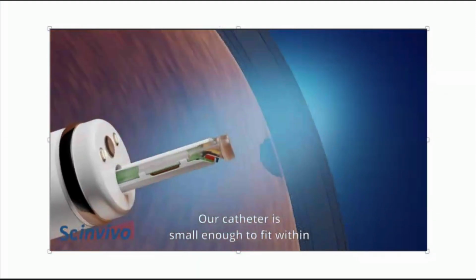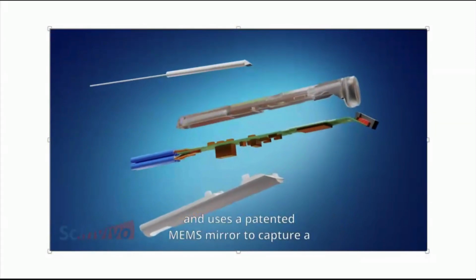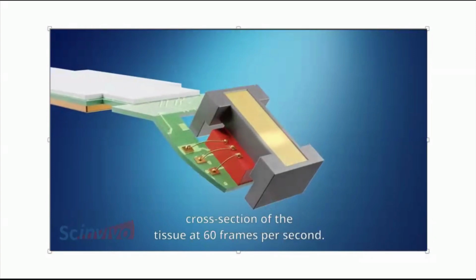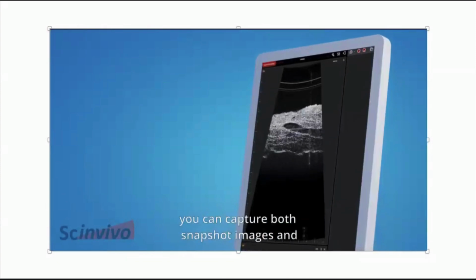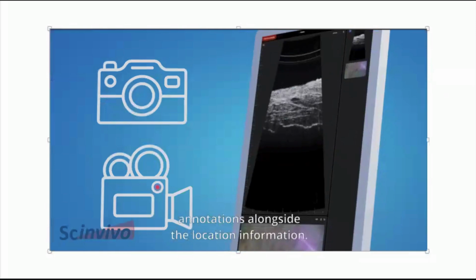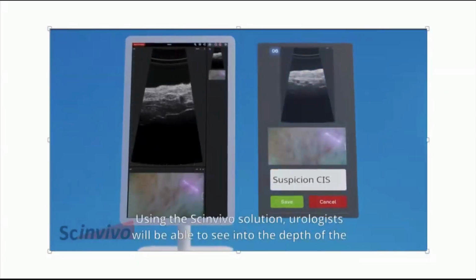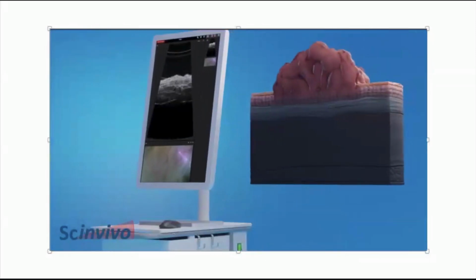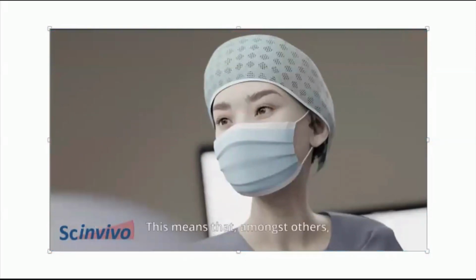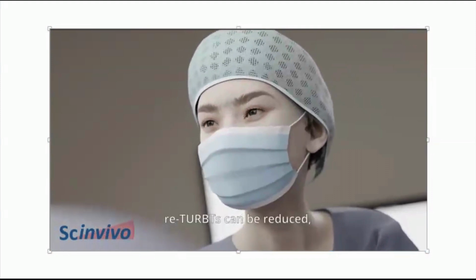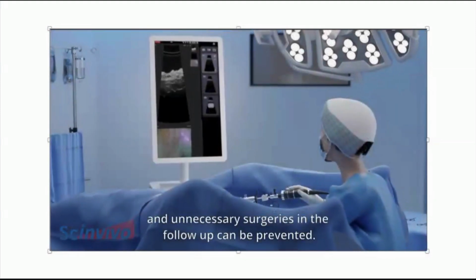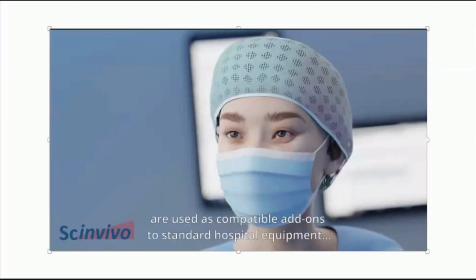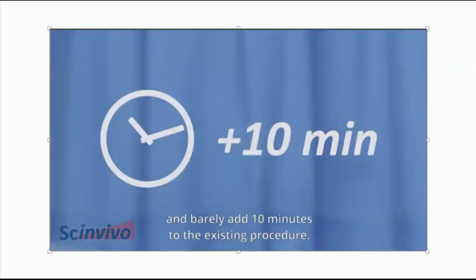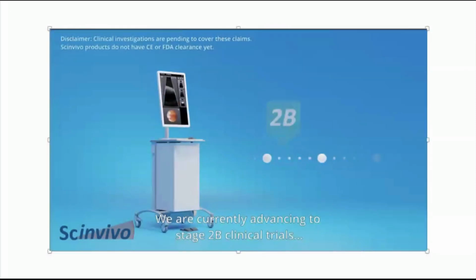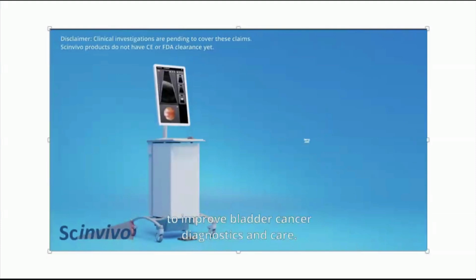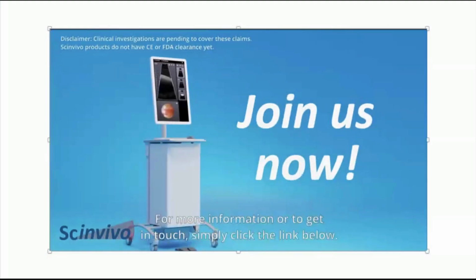tumour. Our catheter is small enough to fit within the working channel of a standard cystoscope and uses a patented MEMS mirror to capture a cross-section of the tissue at 60 frames per second. With the central software on the base, you can capture both snapshot images and videos that can be saved with individual annotations alongside the location information. Using the Scinvivo solution, urologists will be able to see into the depth of the bladder wall in real time instead of just looking at the surface. This means that, amongst others, re-TURBTs can be reduced, bladders can be spared, and unnecessary surgeries in the follow-up can be prevented. The OCT base and disposable catheters are used as compatible add-ons to standard hospital equipment and barely add 10 minutes to the existing procedure. We're currently advancing to stage 2B clinical trials and invite you to join us in this journey to improve bladder cancer diagnostics and care. For more information or to get in touch, simply...